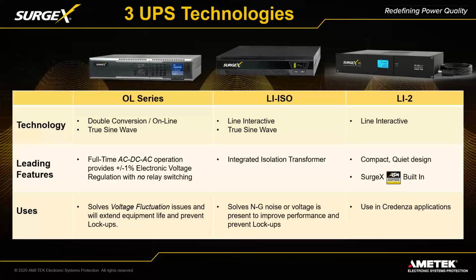So it's a great solution—it solves those voltage fluctuation issues. But like we said, Jimmy, when we were at that WeWork and we plugged the Envision into the outlets, we weren't even in a very tall building, I think we were only on the 3rd floor, but we had terrible neutral to ground voltage in that particular conference room.